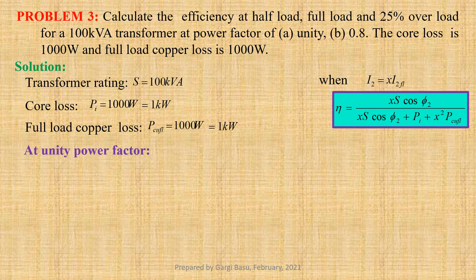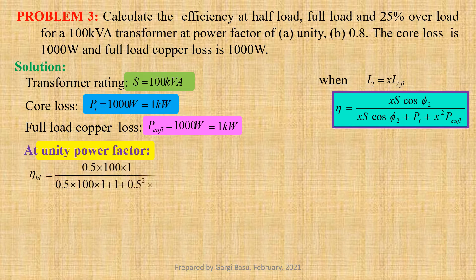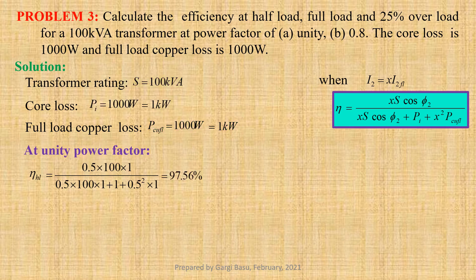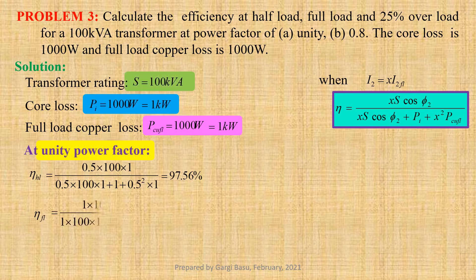At unity power factor and half load, efficiency ETA equals to 0.5 into 100 into 1 divided by 0.5 into 100 into 1 plus 1 plus 0.5 squared into 1, that gives us 97.56 percent. At unity power factor and full load, efficiency ETA_FL equals to 1 into 100 into 1 divided by 1 into 100 into 1 plus 1 plus 1 squared into 1, that gives us 98.04 percent.